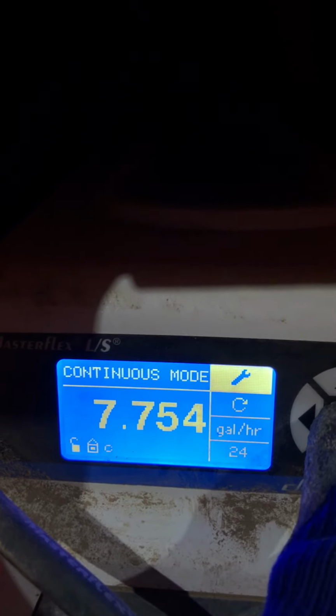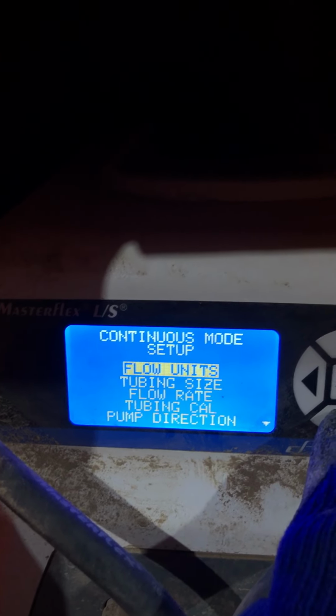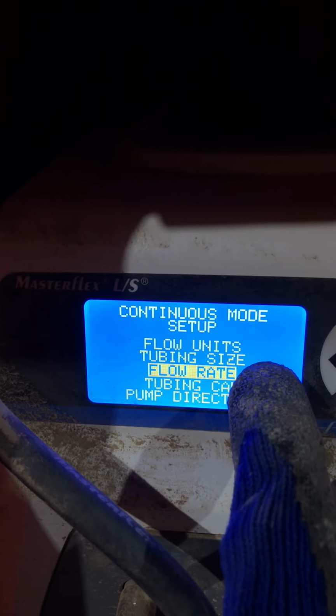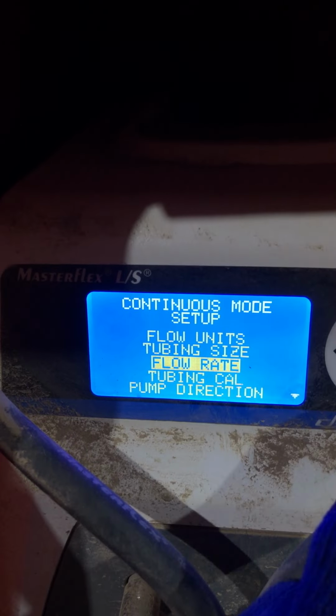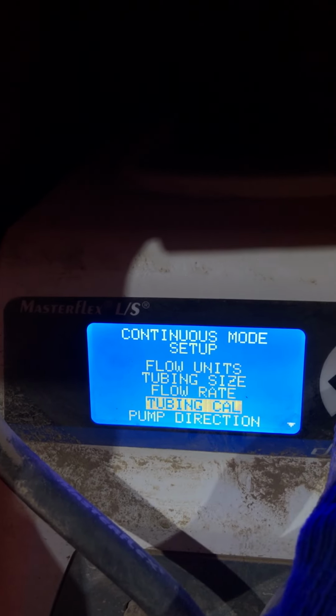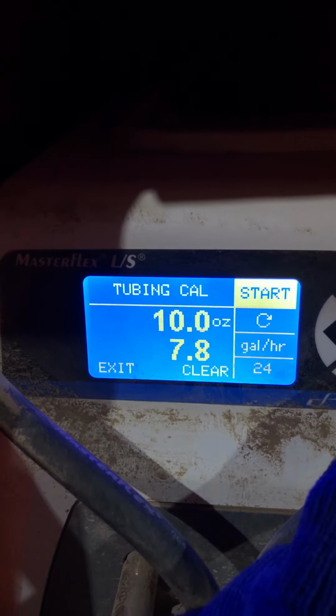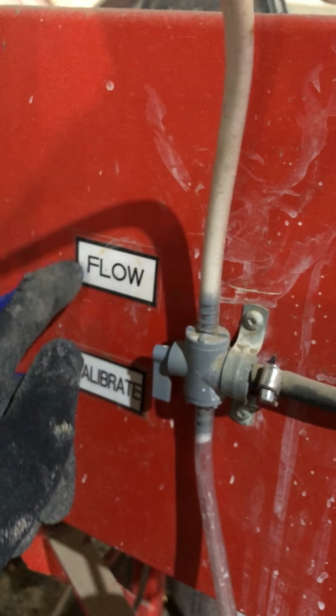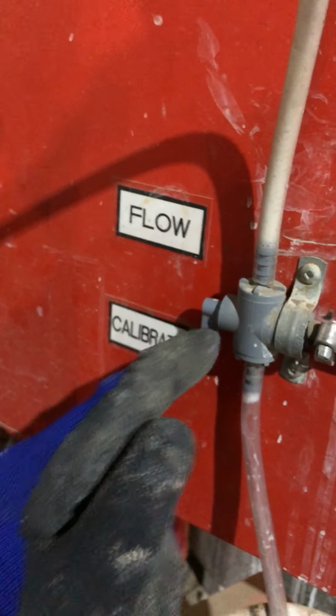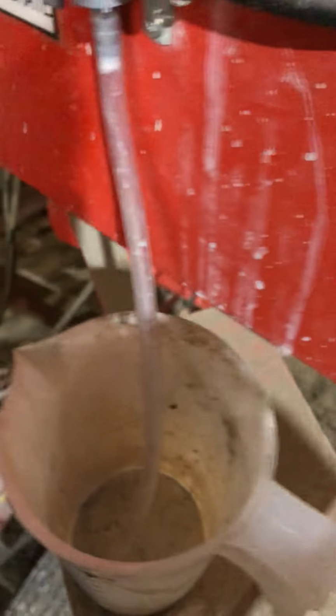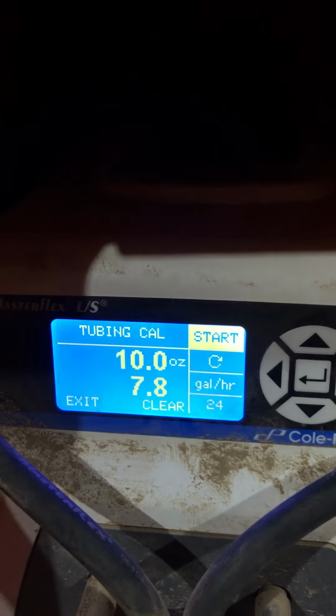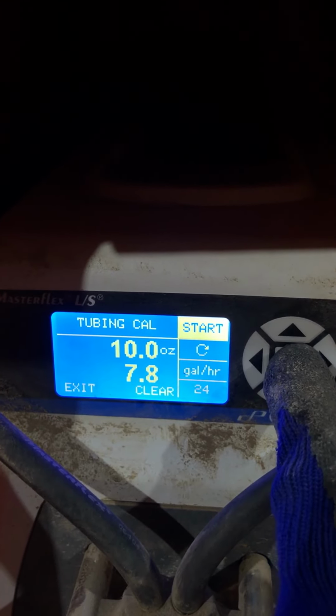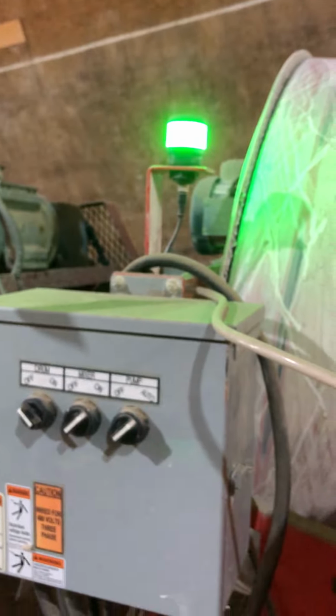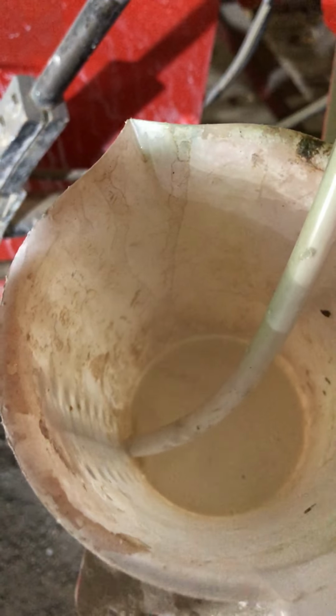So then you go to tools, flow rate would let you input that 7.75, whatever you want. Tubing calibration, and then you go over here and you flip this valve from flow to calibrate. It's already on calibrate. Then you put your little measuring cup at the bottom and then you press start. Green light should come on, pump should run, and it'll be filling the cup.